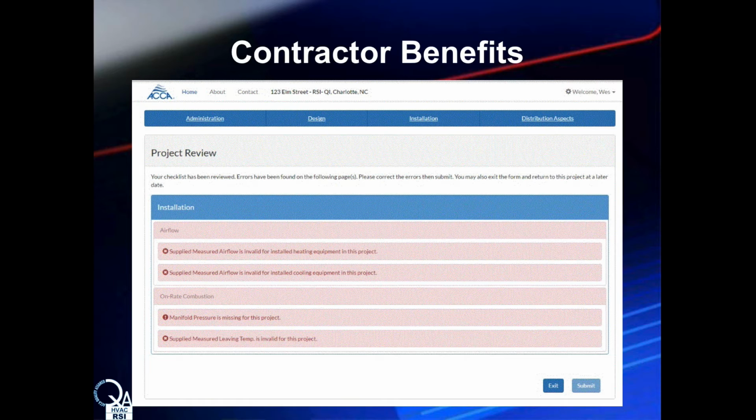For example, abnormally high external static pressure can indicate poor airflow leading to higher energy usage, decreased comfort, and other problems. This informs the manager that those renovations need to be proposed. Or perhaps they were already part of the original proposal and the customer chose not to invest in the duct renovations. Well, this gives you a second opportunity to make that wise investment based on post-installation field measurements.